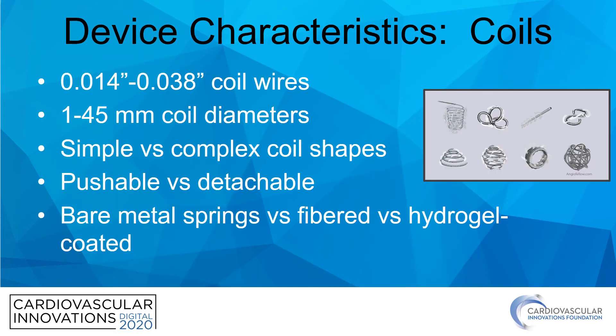Now let's talk about our devices, starting with coils first. There are a variety of coil platforms on the market. Coils can be made up of 0.014 inch wire all the way up to 0.038 inch wire, and the coil diameters themselves can be as small as one millimeter and as large as 45 millimeters. The shapes can be simple or complex varieties, as shown on the right.